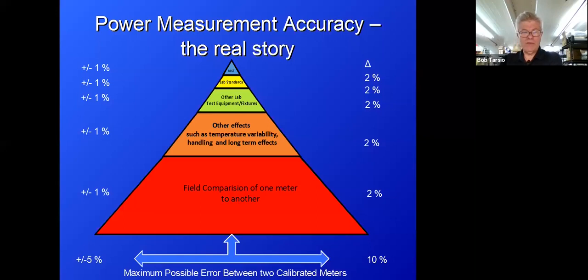But let's think about something. If you've got 4 or 5% error in one meter, and that other meter that you're comparing it against probably has the same delta for maximum error, they could add up in the wrong direction. You have to assume that they will. That means that you could have a plus or minus 10% delta between 2 meters, and they're both within specification, and that would be considered normal. Now that's not typical, because statistically we know that these things generally average out. So guess what? That was well within the statistical error, having a 5% delta.